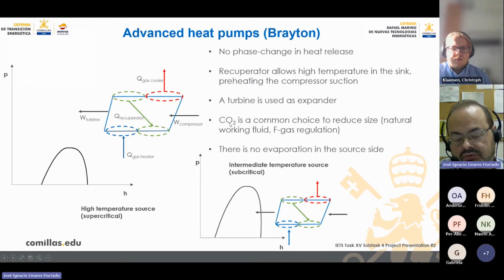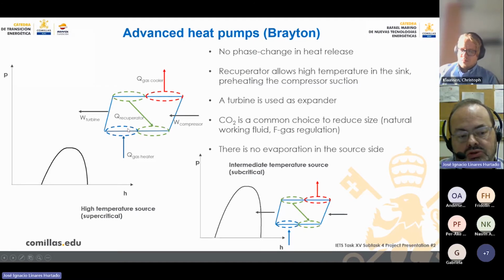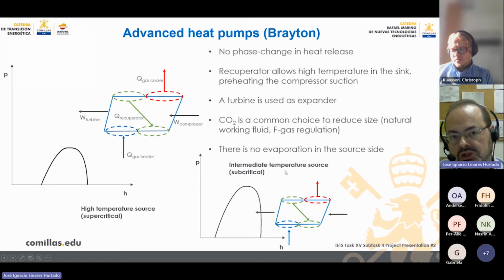CO2 is usually the best fluid for this performance. Moreover, CO2 is a natural working fluid, a natural refrigerant, so it has a low global warming potential, 1 exactly, and 0 ozone depletion potential. Okay, if we have a high temperature source, more or less 100 degrees or higher, this will be more or less the position of the cycle in the pH diagram, above the critical point of the CO2. But if we have an intermediate temperature source, more or less 40, 50, or 70 degrees, we move the cycle to this side. That is, here we are in the gas zone of the CO2, and here in the superheated vapor of the CO2. But in any case, without phase change.